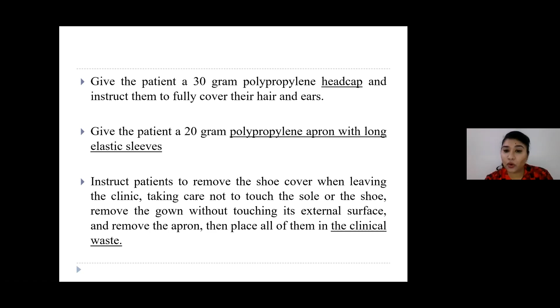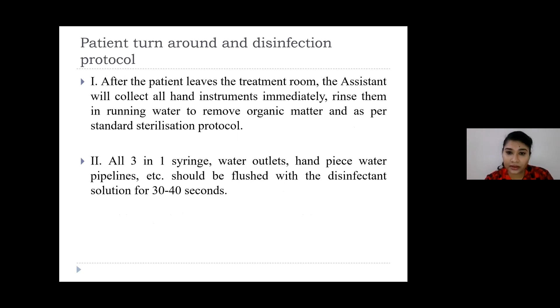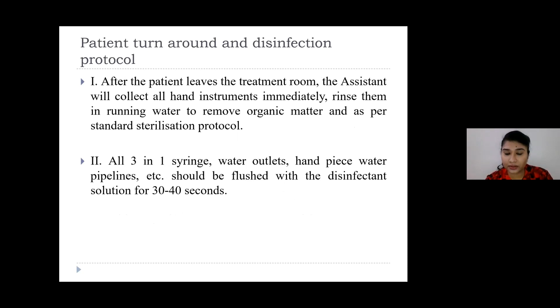Now, when the patient turns around, the actual disinfection protocol starts. As soon as the patient leaves, the assistant will collect all the instruments immediately and rinse them in running water to remove any organic material, as per the standard sterilization protocol we follow. All the three-way syringes, handpieces, water pipelines and tubings, everything has to be removed or flushed using a disinfectant for 30 to 40 seconds. As I've discussed, you can use 0.2% peracetic acid.